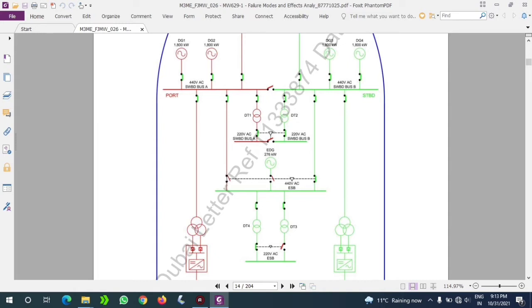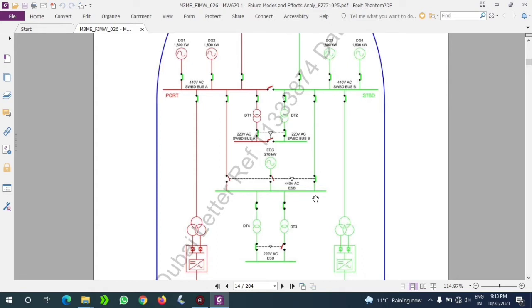But on the other side you can see that the breaker is closed. What you can make out from this is that this bus bar is getting power from starboard 440 volt bus bar. We can change this as per our scenario. Suppose if starboard bus bar failed and port side bus bar is having power, we can close the breaker which is opened in the port side.